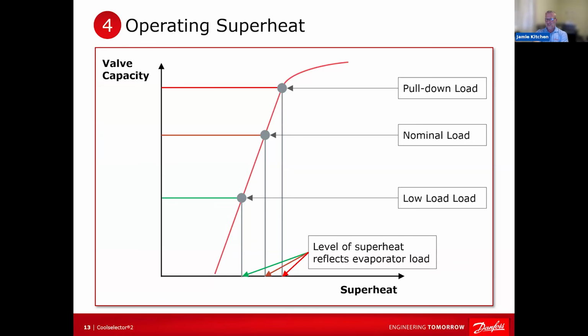So what ends up happening is when the system first starts up, the TXV is going to open up and you're going to start operating somewhere around nominal load, maybe above and maybe below. And as your load gets pulled down, the TXV is going to close until the space is satisfied, and then bang, it shuts off. And then it sits for a while, heat builds up, and then bang, it opens up again. It's going to open up, and then slowly it's going to come back down again. And so that's how the operating sequence works. Now, if you adjust superheat, you're not really tilting it. You're just sliding that graph this way, all right?